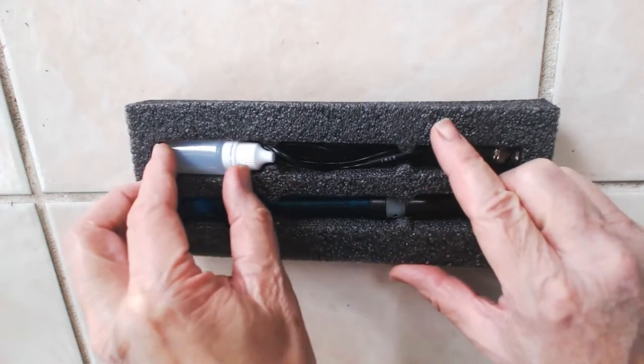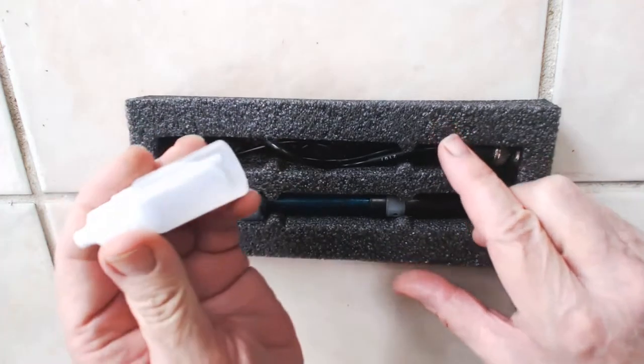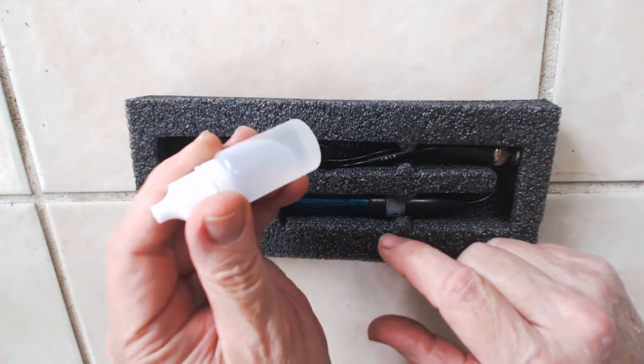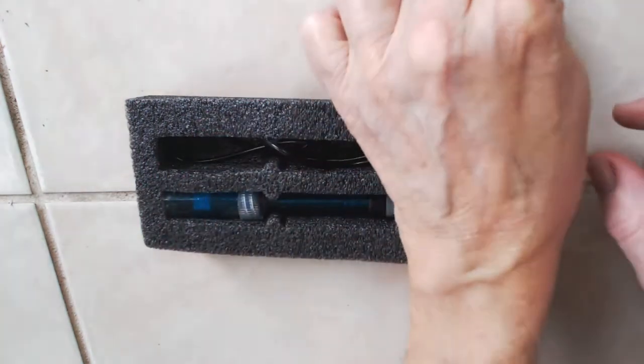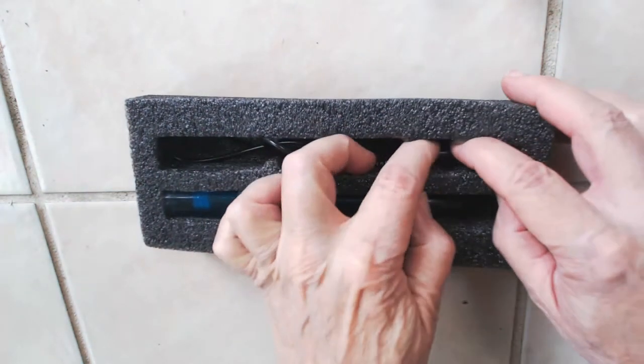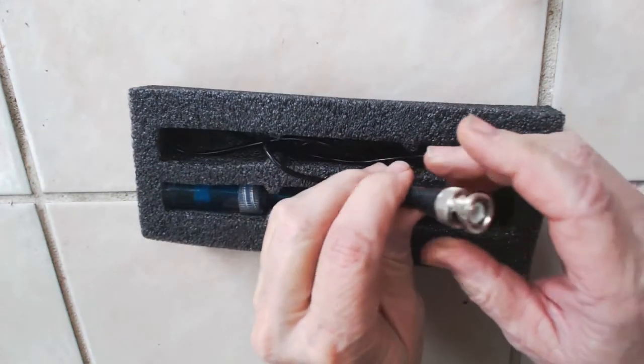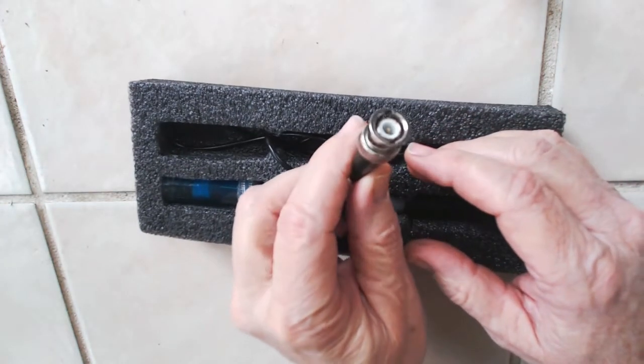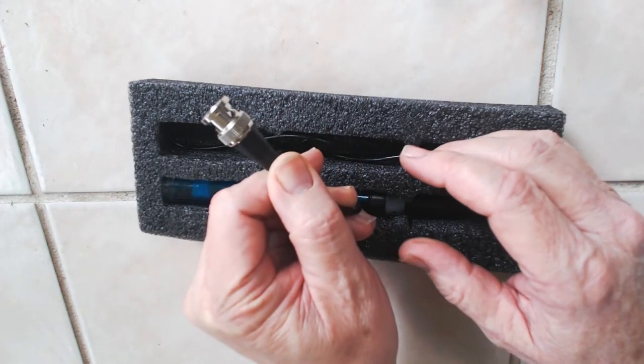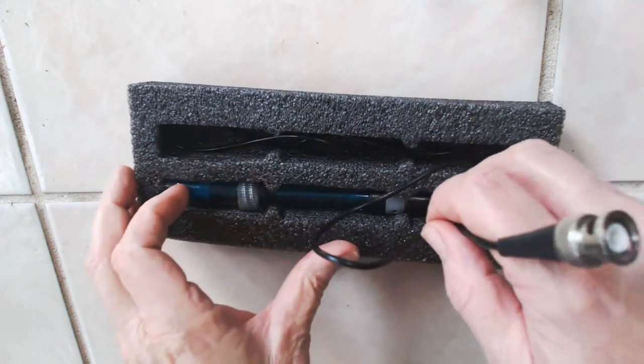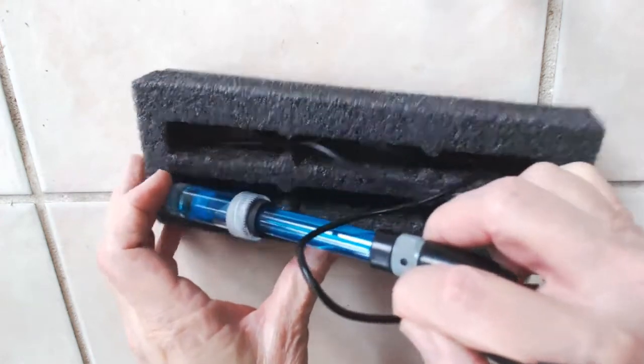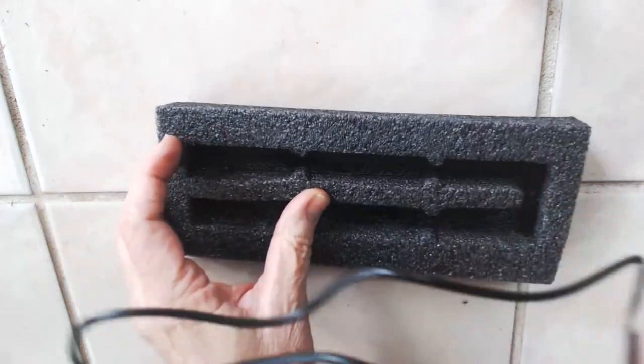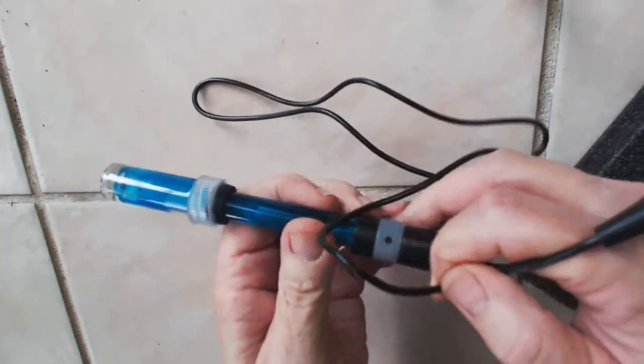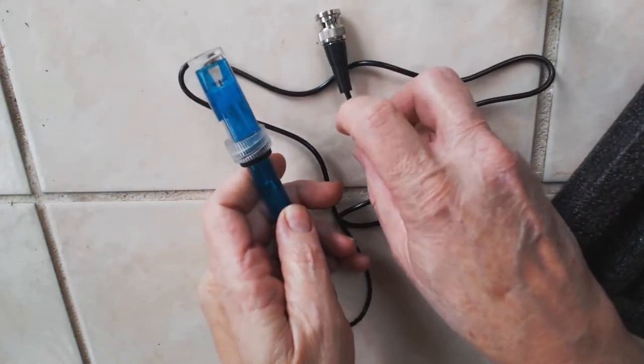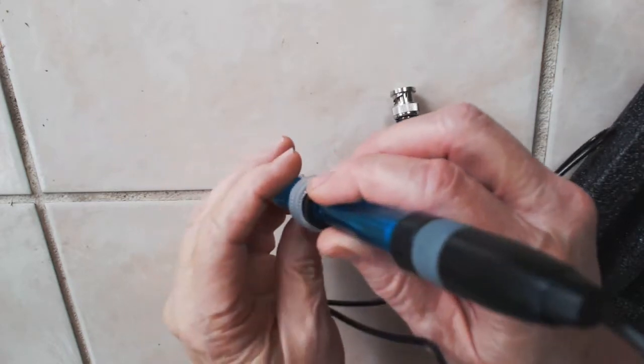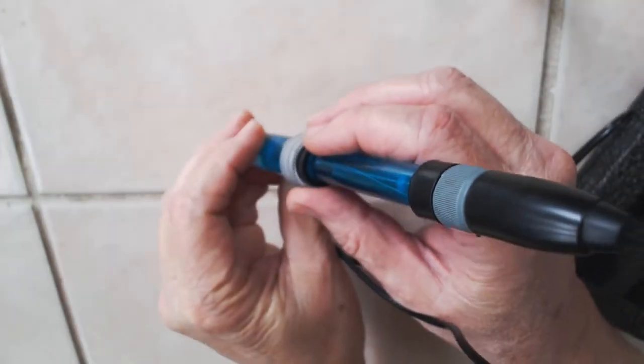Well, at the heart of any pH meter is the actual probe. The little bottle I pulled out here is a solution that is provided with the probe to keep the probe tip wet at all times. Never let a pH probe dry out. The probe I have here has a BNC connector. You can also buy them with SMA connectors. As you can see here, this probe has a little cap on the end of it. That holds the fluid and makes sure the probe stays wet at all times. This fluid is a special fluid, and you need to buy that. It's not tap water, so you definitely want to buy the proper fluid for storing your probe if you happen to run out of the fluid that comes with the probe.